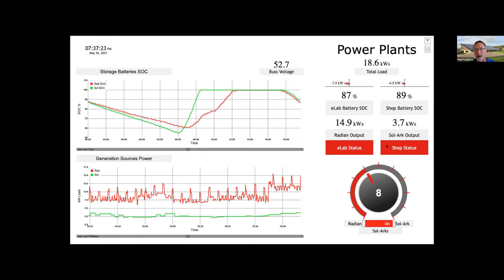To control those systems from backfeeding each other, this program works by telling one to be in grid forming mode and the other to sell to our own grid. Every second we give it a new value to sell so it doesn't backfeed each other. It works pretty well. We have another small microgrid up on Mauna Loa, our Mars Habitat, which uses the same systems as here at the ranch: solar and lithium ferrous phosphate batteries, plus a hydrogen fuel cell as backup.